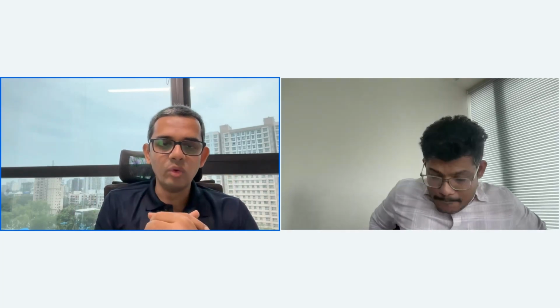Wow, that's quite revealing. 3 to 4 crore rupees on a back of the napkin calculation for just a 0.05 improvement in PUE, if I understand Anurag correctly. Sorry, Rajan bhai, it is 1.5 to 1.7 CR. Okay, sorry, 1.5 to 1.7 CR, still a difference, yeah. Very, very big, significant difference for just a 0.05 improvement in PUE. So that's the power of what PUE is telling us.